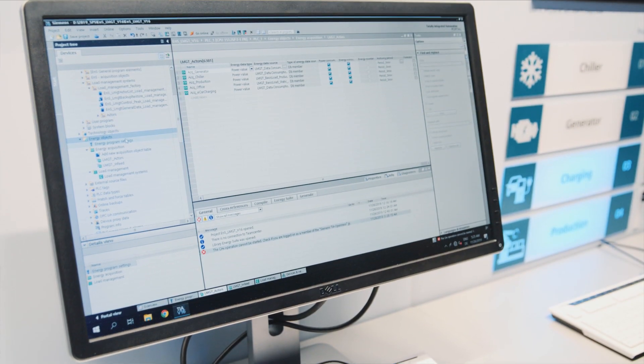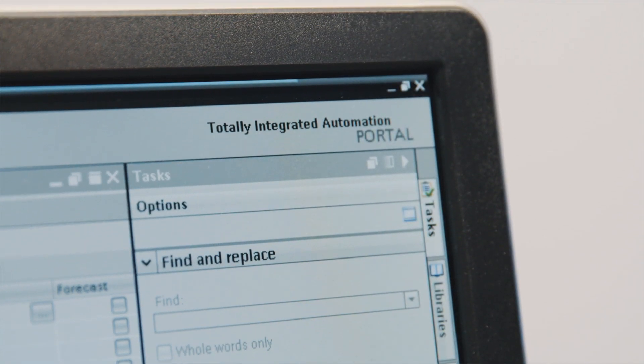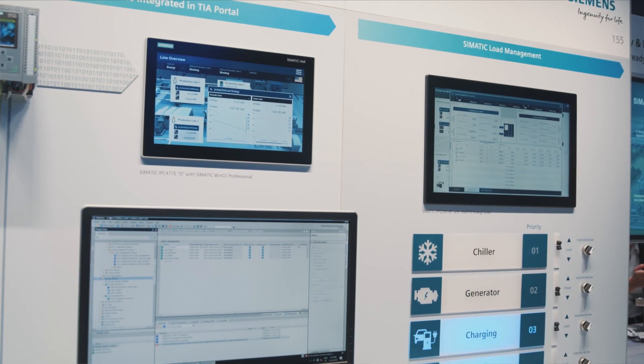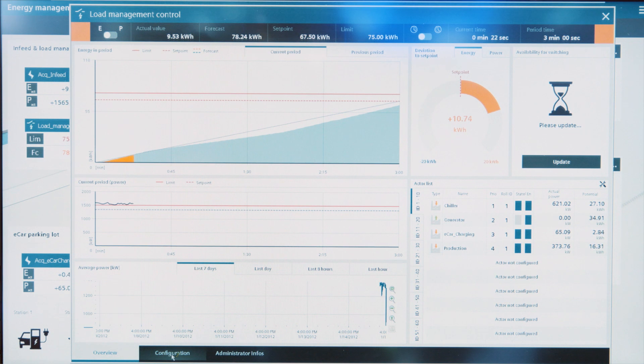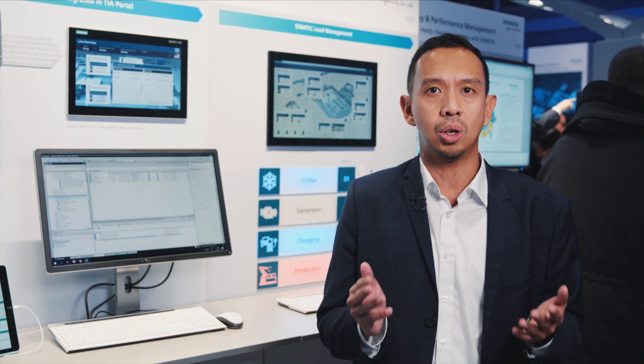PLC-based load management in the SIMATIC Energy Suite is simply configured via editors in the TIA Portal v16. The corresponding PLC program is then generated automatically and the visualization is created. The load management calculates the consumption using an integrated forecast algorithm and switches consumers and producers off or on in order to distribute power consumption evenly, thus avoiding excessive peak loads.